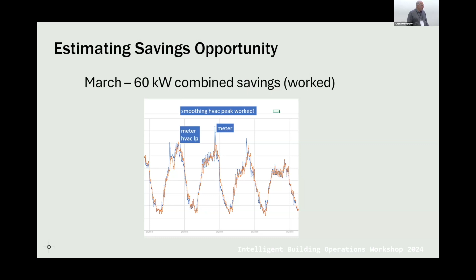In this case, you compare the peak of the meter with the benchmark — what we did was take the whole building, subtract off the HVAC, and then replace the HVAC with the low pass filter version. You can see in this case it worked: you got 60 kilowatts of combined savings if you just did the thermostats and ignored the whole building meter.